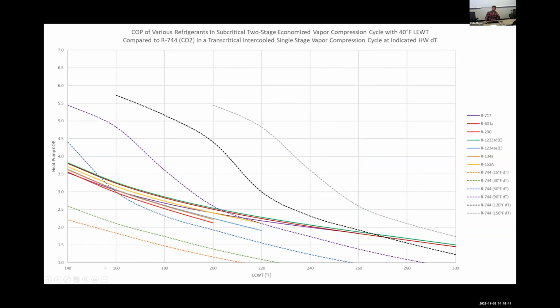So this chart is hot water supply temperature, which is leaving condenser water temperature, relative to efficiency in terms of COP. So in this case, higher is better. All the dashed lines are CO2. So you can see how CO2 can potentially be much more efficient, but qualified in the legend by color is the amount of differential temperature on the heating system. So it's only more efficient if you have very high differential temperature. If you have normal differential temperature, it's actually less efficient.